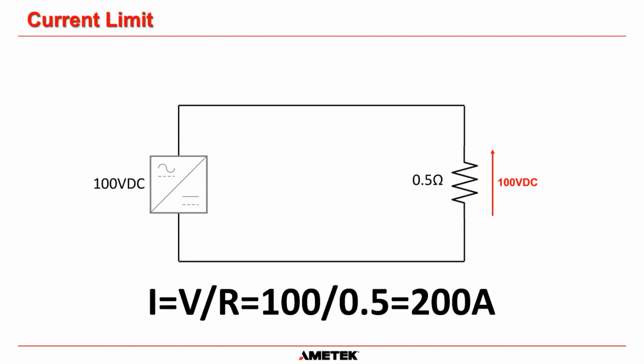So it's important to remember, we cannot directly change the current. We have no control over the actual current from the charger. The only thing that we can control in the charger is V. Now remember, we can't control R because that's the plant load. Whatever the plant load is, whatever the plant load is. And we can't change the I. Okay, the only thing we can change at the charger is V. Okay, and that is how current limit works. It's actually changing the voltage to keep the current at what we want it to be.